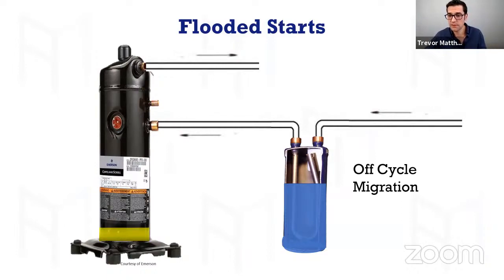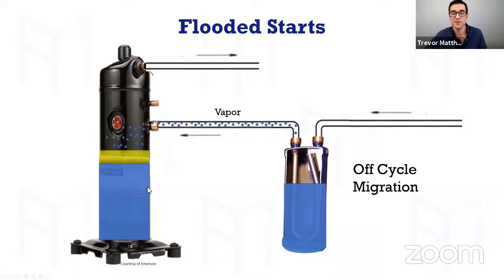So this migrates as a vapor into the compressor. Now, all of a sudden, the compressor starts to fill up with refrigerant because it condenses in the oil. So if you ever look in a compressor at the sight glass and it's filled, that's a bad sign. More oil is bad, because you could have refrigerant under there or too much oil. You need to understand that. And then all of a sudden, this compressor is full of liquid refrigerant. And then bam, you get a slug, or this is a flooded start. A slug is when you break something. If you don't break it, that's called a flooded start. You need to know the difference.